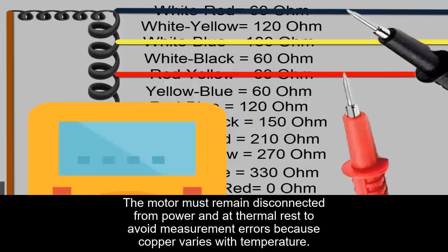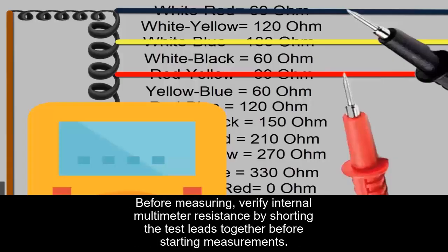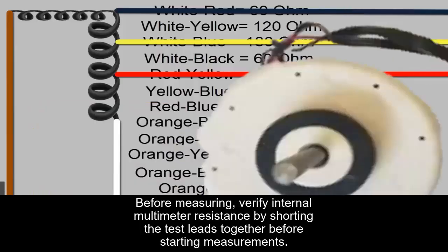It is essential that the motor is completely disconnected from the power supply and at thermal rest to avoid measurement errors, since copper resistance varies with temperature. Before measuring, it is recommended to verify the internal resistance of the multimeter by shorting the test leads.